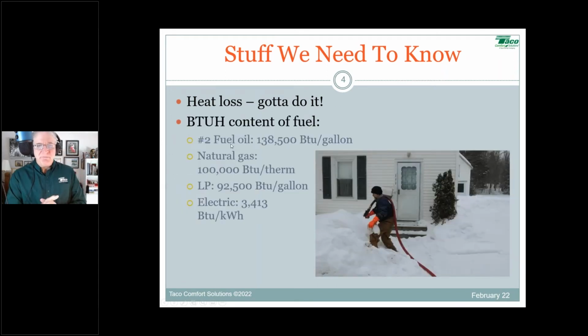It's also good to know the BTUH content of different types of fuels depending on what you're using. Fuel oil is 138,500 BTUs per gallon, and there are figures for natural gas, LP, and electric as well, depending on what you're working with. You'll need that information to do the math, and if you love math, you're going to love the formula for this one. So you have to have a reasonably accurate heat load, and you need to know the BTU content of the fuel you're using.